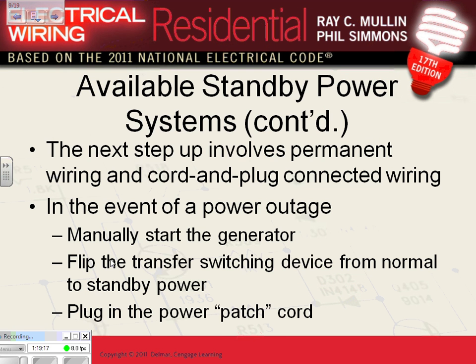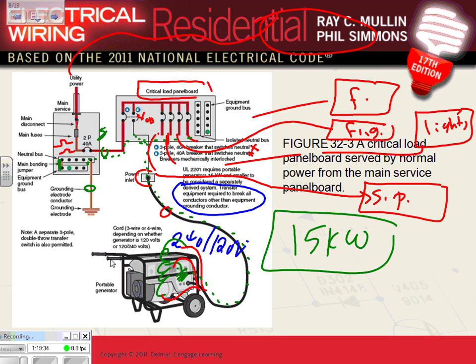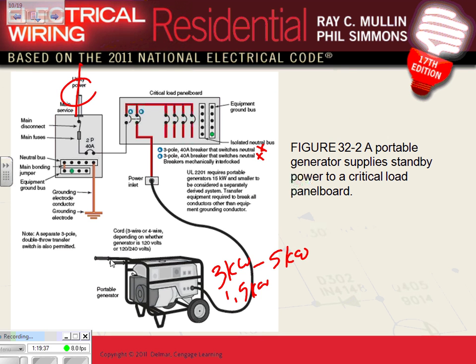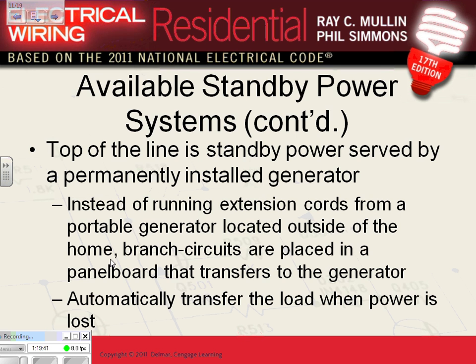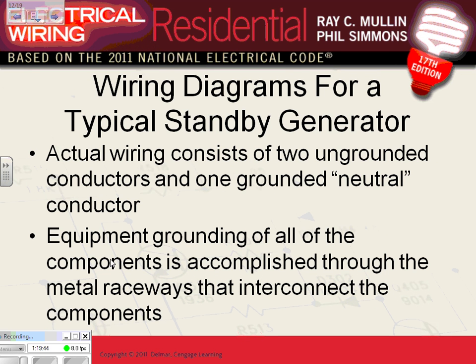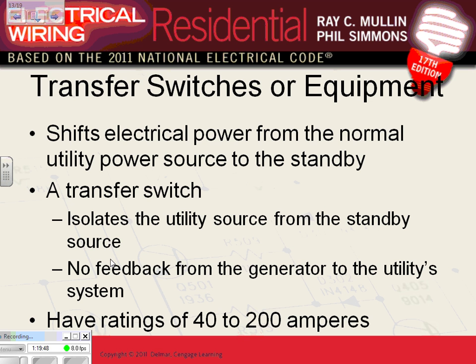Okay, we talked about this one: manual starter generator, flip transfer or plug-in. You can start a generator, guys, by the plug, the easiest, cheapest way. Then you can go to a manual transfer switch as we wired it, or you can have a non-manual transfer switch, an auto transfer switch, where you can be anywhere and your generator can start. Okay, transfer switches. We talked about separately derived systems, and we will continue talking about them as we go, guys, in the commercial and industrial. They don't want you to kill the lineman. That's why you have to have isolation: an auto transfer switch, manual transfer switch, or interlock circuit breakers to isolate yourself from the grid.